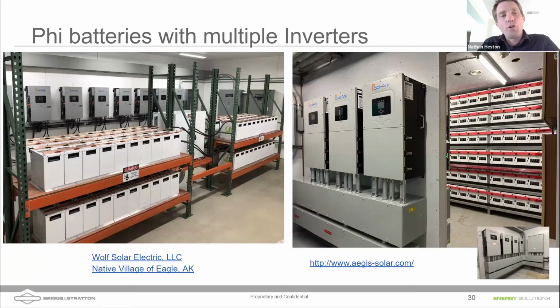I've often wondered, people will ask us, what kind of routine maintenance should we do for batteries? What kind of routine maintenance should we do for inverters? Is it a good practice to take maybe compressed air and blow through those fan systems, or could that damage the units? I don't think you really need to do that with a Sol-Ark unit, because the air system is for cooling, but it doesn't blow air through the internal. Understood that it's isolated on the back. Yeah. Okay, in the interest of time, I'm going to keep going.